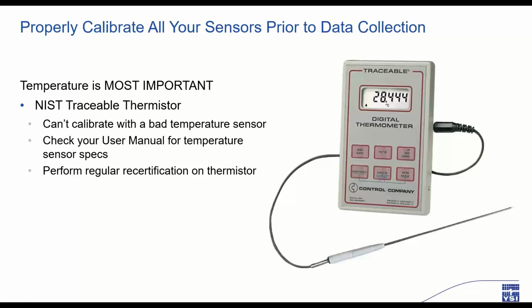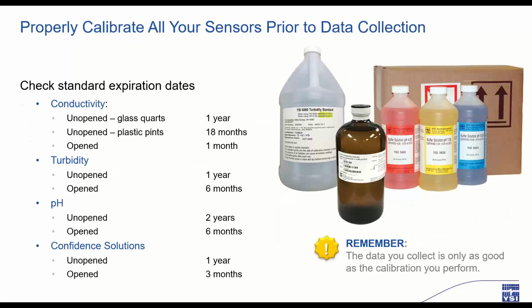Also, make sure to send your certified thermometer in to a lab to make sure that it remains within specifications. Typically, this might be once or twice a year, depending on the manufacturer of that thermometer. Next, you need to make sure that you're always using fresh calibration standards or solutions. Check the manufacturer's expiration date and note when the bottles were opened. The expiration date on the bottle is generally for an unopened bottle and can differ once the seal has been broken. People sometimes ask if they can use standards that are only expired by a month or two.